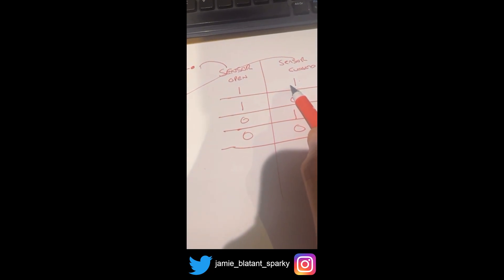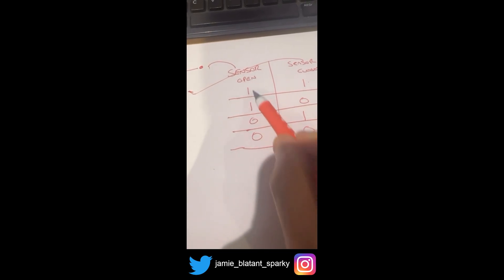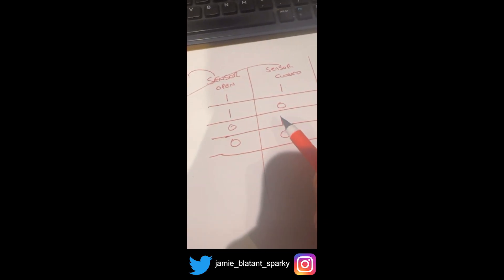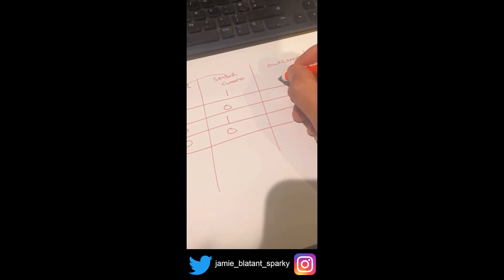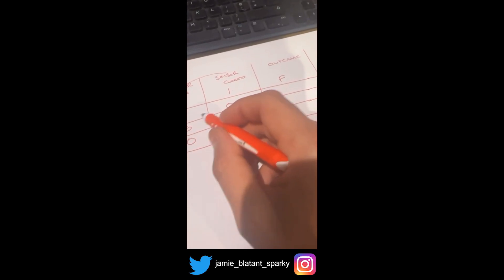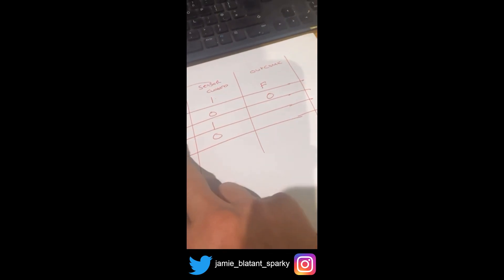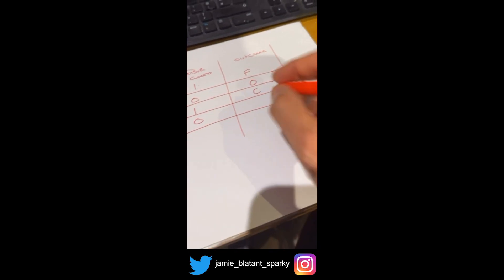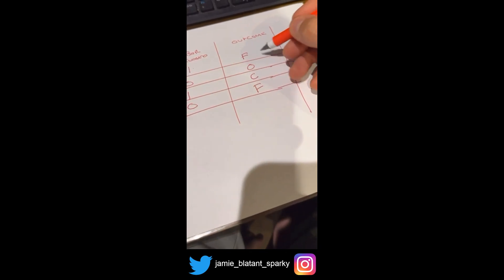Both sensors could be detecting something — that's one possibility. The open sensor detecting something and the closed sensor detecting nothing would mean it's open. The open sensor detecting nothing and the closed sensor detecting something means it's closed. Then you'd have zero and zero where no sensor detects anything. The outcomes: if they're both on it's a fault; open sensor on means it's open; closed sensor on means it's closed; both off means it's faulty.